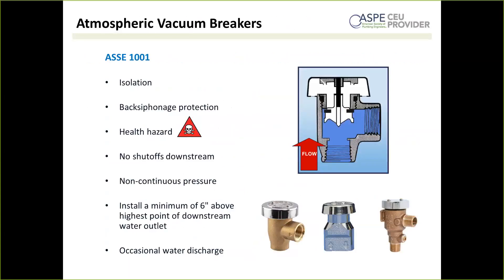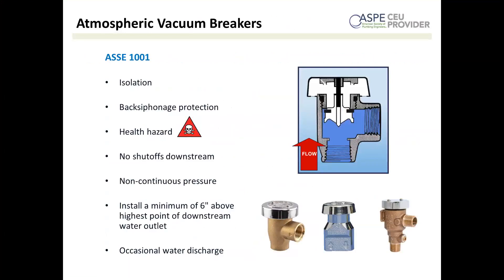The first device is an atmospheric vacuum breaker, ASSE standard 1001, typically for isolation — protecting hazards within a property. It's a point-of-use device that protects from back siphonage only, but can be used for health hazards. When you turn your water on, water causes the float to rise and seal the atmospheric vent. If you get a back siphonage condition — negative or sub-atmospheric pressure — it sucks that float back down, breaking the vacuum. This way it siphons in air rather than potentially contaminated water.